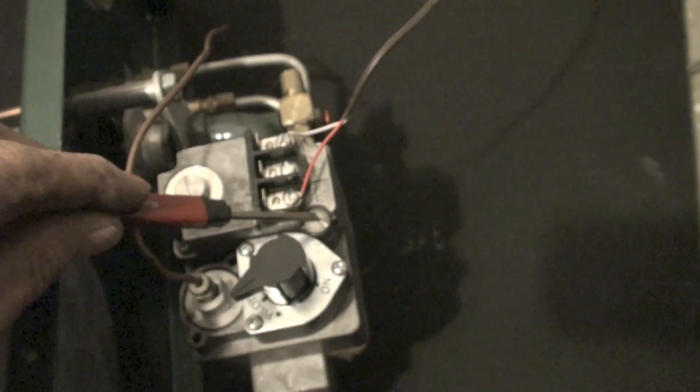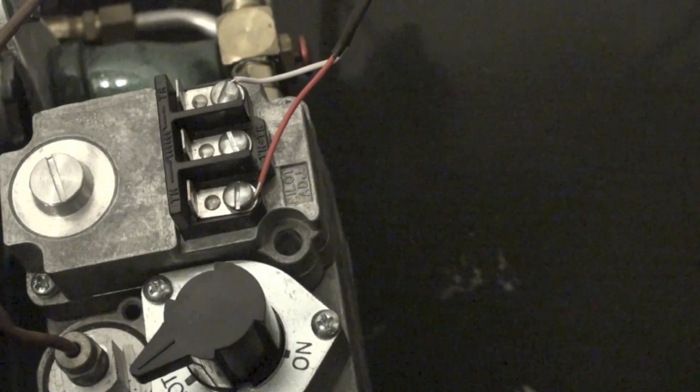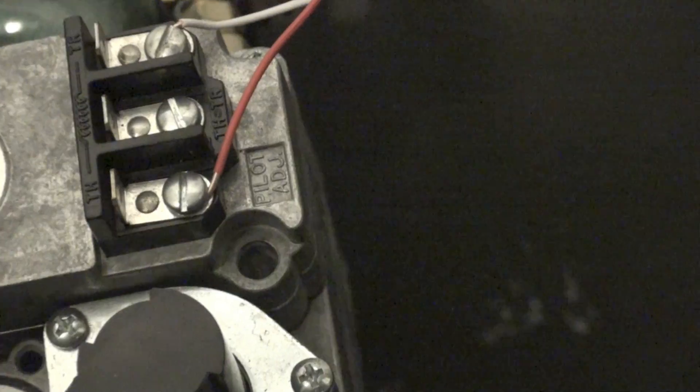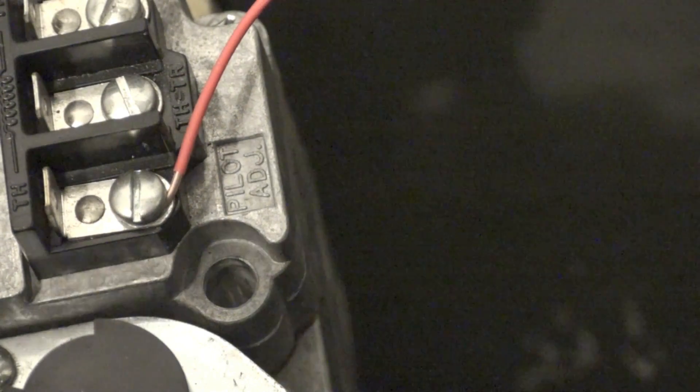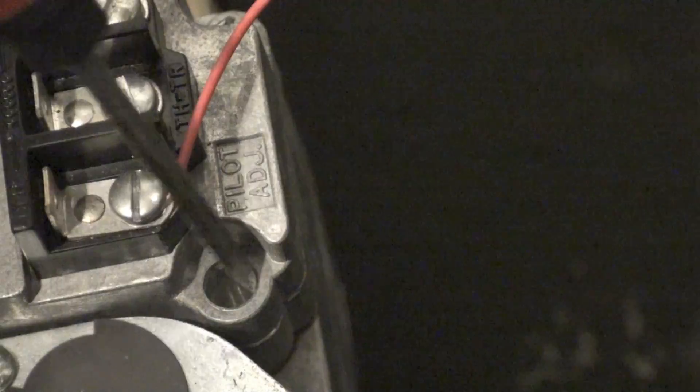Okay, here's a pilot adjust screw. That's just a cap. I'm going to take it off. Okay, now we can see the pilot adjust. Notice it's noted right beside it that's pilot adjust. And it takes a very small screwdriver, a little thermostat screwdriver. And there's a little slot head down there. And you can move it back and forth.